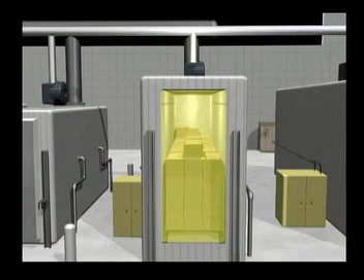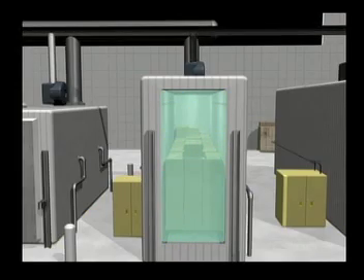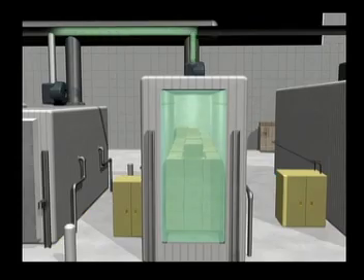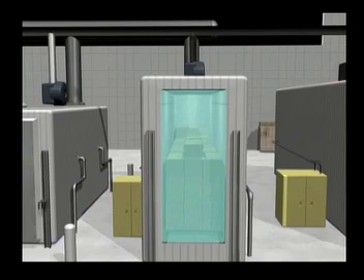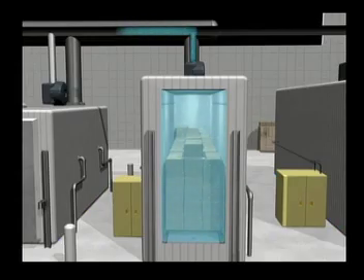Next, virtually all of the remaining ethylene oxide is removed in a step called gas washing. This involves injecting air and nitrogen into the chamber where they mix with the ethylene oxide. This mixture is then pumped from the chamber to the scrubber. This process is critical to reducing the concentration of ethylene oxide to below explosive levels and is repeated several times until there is only a trace amount remaining.